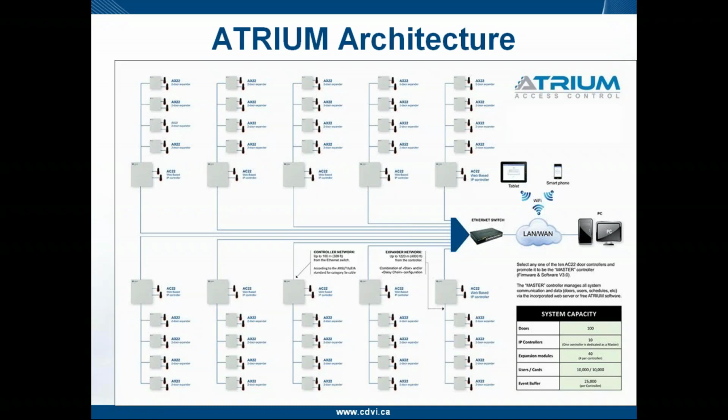So these are some of the thought processes that I put forward to be able to justify what is an expander. Why am I doing an expander? It's because it's convenient. It's only one cable run. It's local to the expander the controller is connected to. The flip side of the coin, well, no, I have in the back of the warehouse another switch there, and there's plenty of ports. I want, as much as possible, if ever there is a failure, while the door will continue working, access control will connect the panel as a subcontroller to the master and have it manage the doors there.